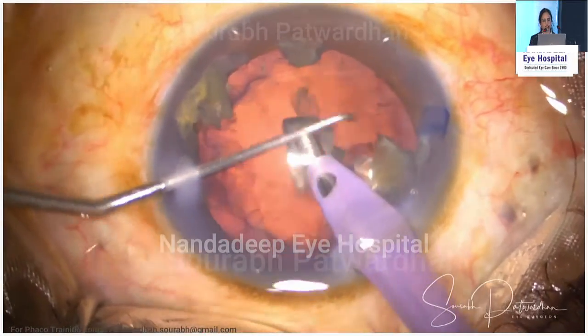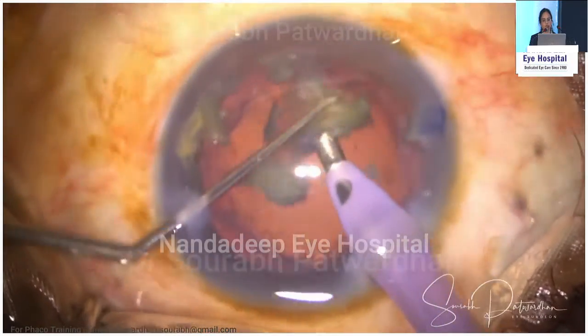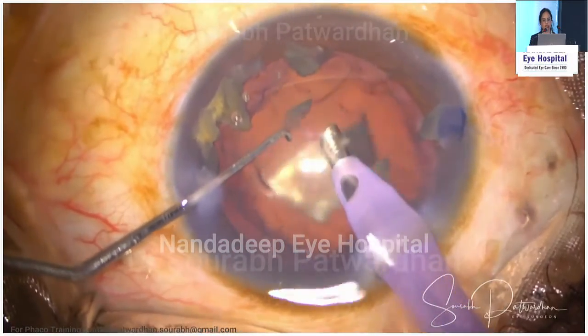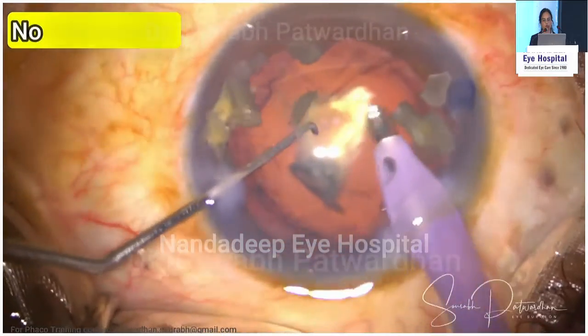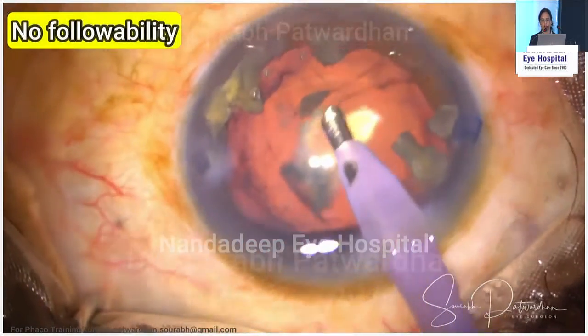So see, in this case, the surgeon is doing the surgery, the pieces are well following, and suddenly the pieces are not following the Phaco probe. And there might be an occlusion sound that you might hear.